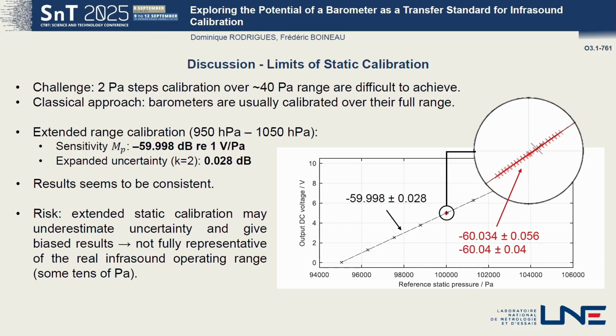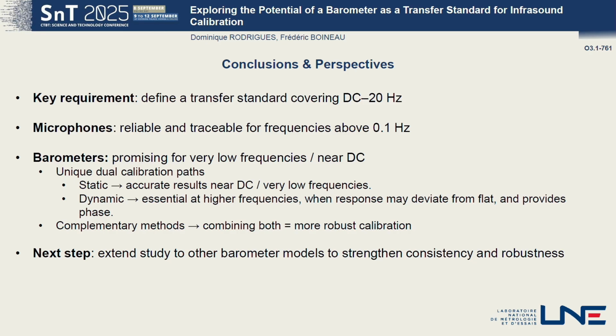Okay, it's time to conclude. The key requirement for this study was to define a transfer standard covering the full infrasound range from DC. As I said in the introduction, microphones play this role very well for high frequency, typically above 0.1 hertz. Here the barometers can be seen as a promising candidate, because the main advantage is that we can use two calibration paths. The static method provides very accurate results near DC and ultra low frequencies, and the dynamic calibration method becomes essential at higher frequencies when the response may deviate from the flat response, and it also provides the phase information, which is important too.